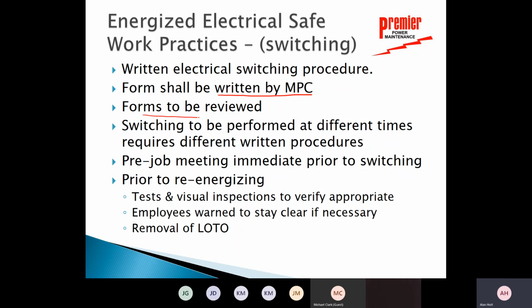Those forms have to be reviewed internally. Big key: it's not just an internal review. You are responsible for your electrical work safety, so you have to be doing reviewing also. If they do switching at different times, let's just say that for one section of the area we're going to work on they want to do switching at 8 o'clock in the morning, but they have a little difficulty in getting some other portion down, so that's going to be done at 10 o'clock. They have to be done on different written procedures, okay? So they've taken that step to reduce the possibility of human performance errors.